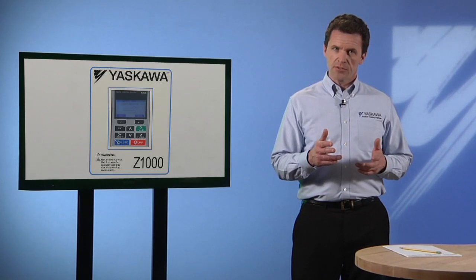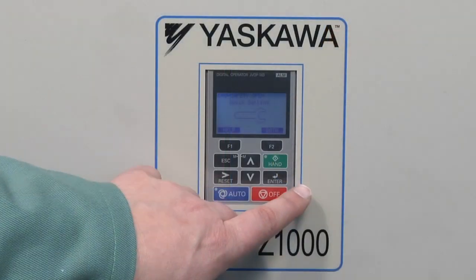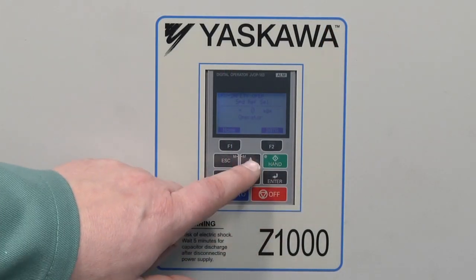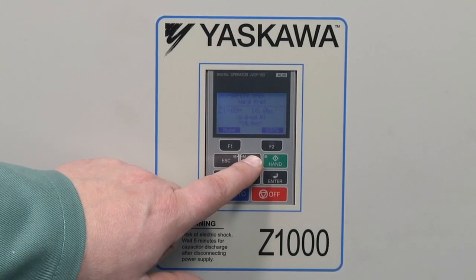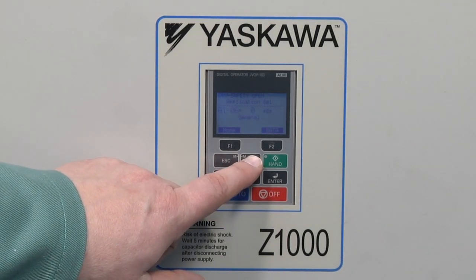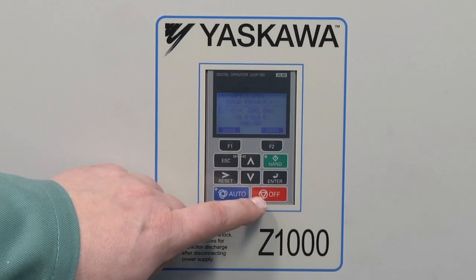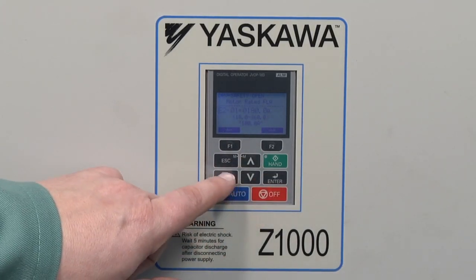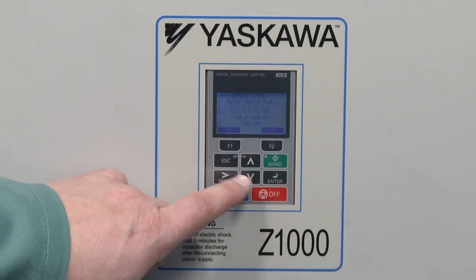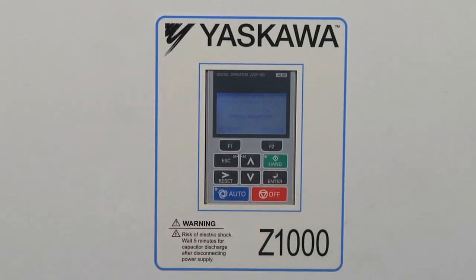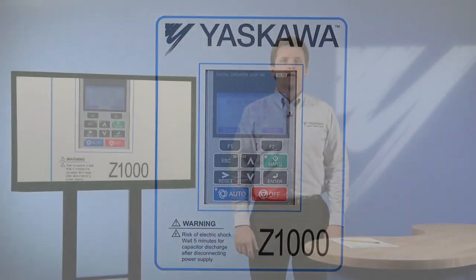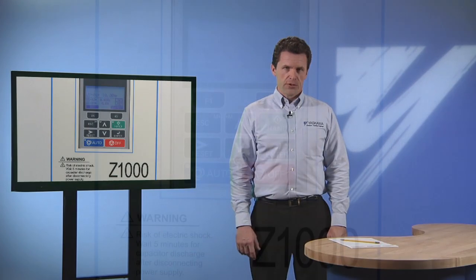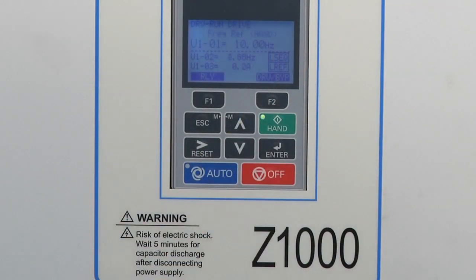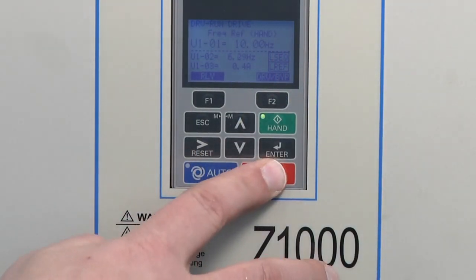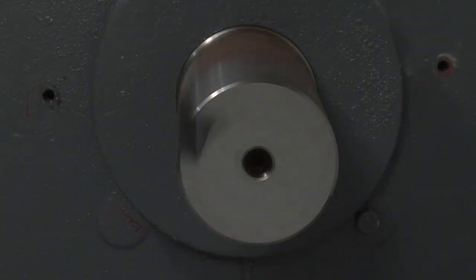We're just about to check motor rotation. Begin by going through the Quick Set menu on the drive's digital operator and adjusting any parameters that need to be adjusted. Be sure that full load amps are adjusted to the full load amp capacity on your motor's nameplate. Now we're going to check motor rotation. If I hit the hand button on the keypad and then the off button, I should get the motor spinning for a moment, just long enough to see if it's turning in the proper direction.